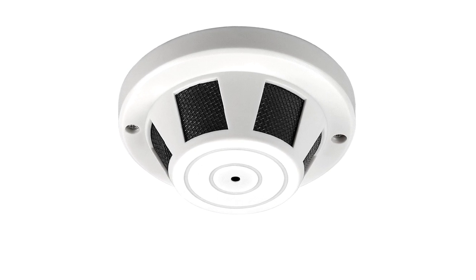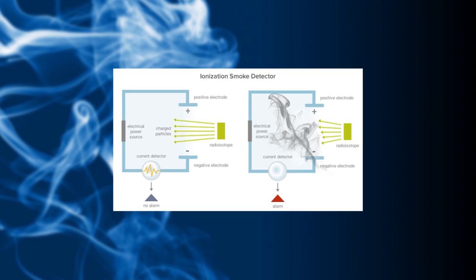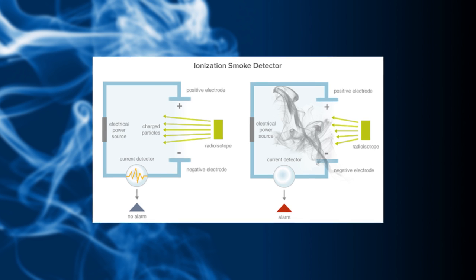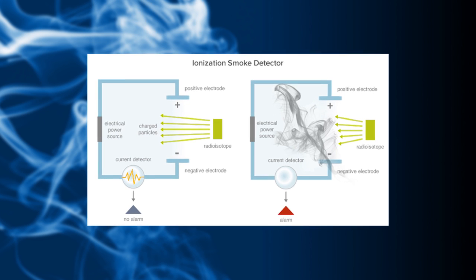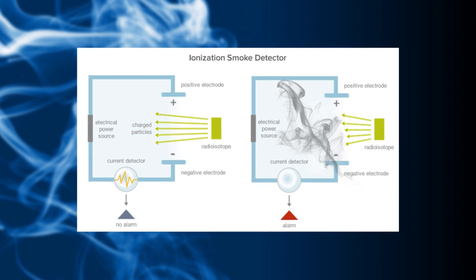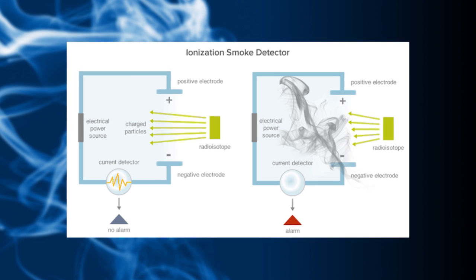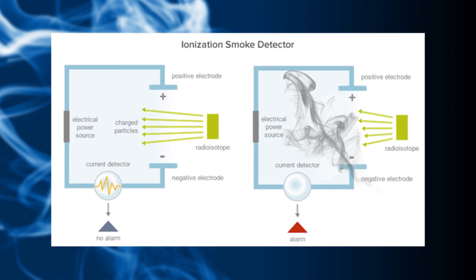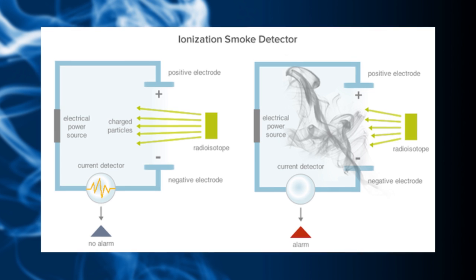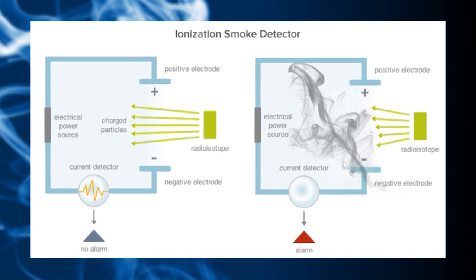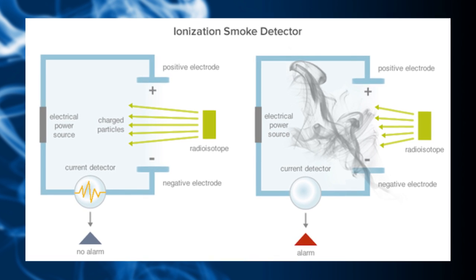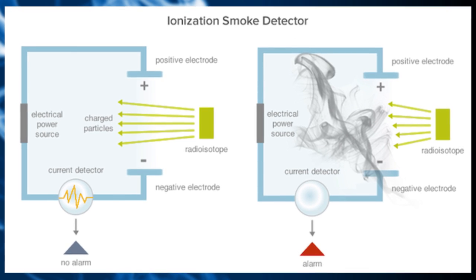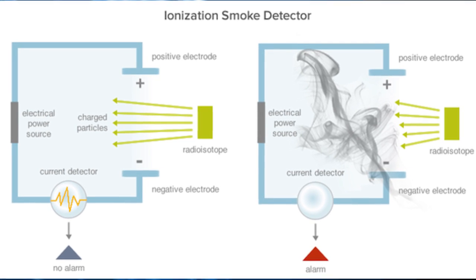This system creates a small electric current. When smoke enters the chamber, the particles attach themselves to the charged ions and restore them back to a neutral electrical state. This disrupts the electric current and an alarm is triggered. Hot air can also change the rate at which ionization occurs within the chamber, and this will also trigger the alarm. Ionization detectors are much more common than photoelectric detectors because they are less expensive and better at detecting smaller amounts of smoke that come from fast flaming fires.